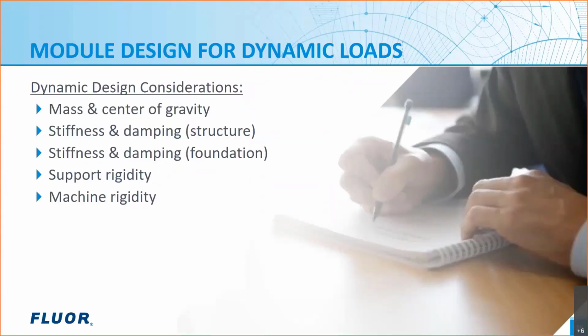Now let us look at the fundamental considerations in a dynamic structural analysis. Mass and center of gravity for the structure are computed based on the analysis model. For the machine, this information should be requested from the machine supplier. For the structure, stiffness is computed based on the analysis model. Damping is applied using a low-end value of a damping ratio. For the foundation, stiffness and damping are determined based on the geotechnical report and proposed foundation.